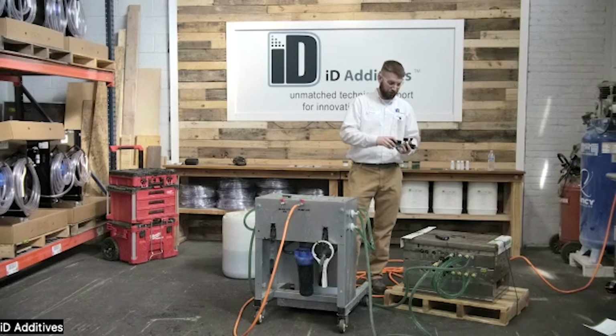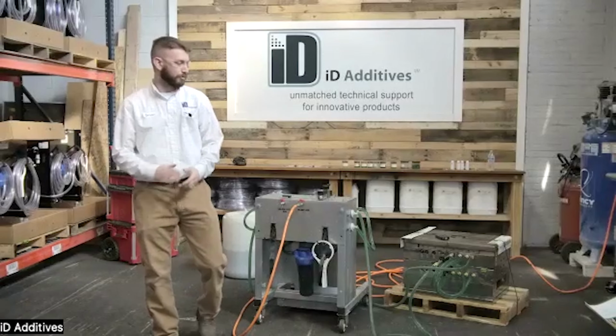I think it read like 6.2. The tolerance was at 5.3, but in the beginning I said I can cheat by just turning this. So what I'll do when we wrap up, I just didn't want that compressor to go off. I'll turn it on, set it at a set point, benchmark what it is in the beginning, let it run for an hour while we're having lunch, and check it later to see what it's doing.